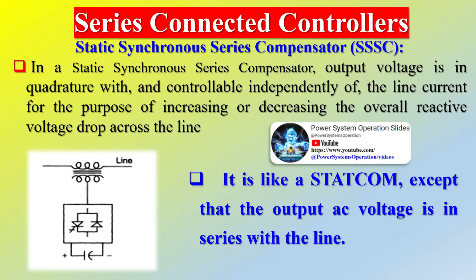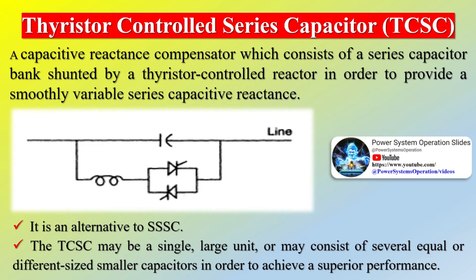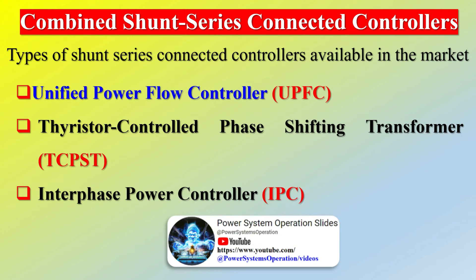Shunt controllers could be a variable impedance — capacitor, reactor, etc. — or a power electronic-based variable source, or a combination of both. They inject current into the system. If the current is in phase quadrature with the voltage, the controller supplies or consumes reactive power; any other phase involves control of both active and reactive power. Combined series-series controllers could be a combination of separate series controllers or a unified controller — the interline power flow controller — which balances real and reactive power flow in the lines. Combined series-shunt controllers could be separate series and shunt controllers or a unified power flow controller, injecting current with the shunt part and voltage in series with the series part. When unified, they exchange real power between the series and shunt controllers via a power link.